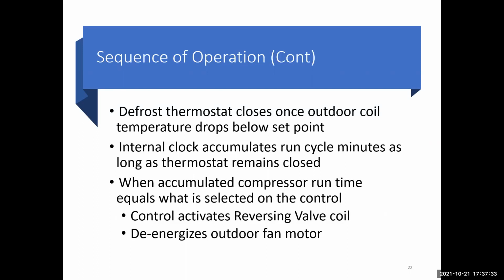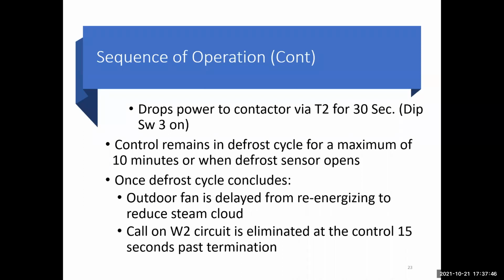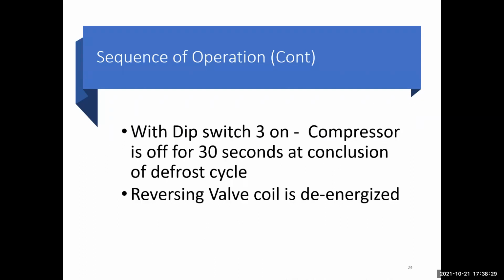When accumulated runtime equals what is selected, the control activates the reversing valve, de-energizes the outdoor fan motor, and drops power to the T2 for 30 seconds. As long as dip switch 3 is on, the control remains in defrost cycle for a maximum of 10 minutes, or when the defrost stat opens, right around 65 degrees. Once the defrost cycle concludes, the outdoor fan is delayed for re-energizing to reduce steam cloud. A call on W2 is eliminated at the control 15 seconds past termination. With the dip switch on, the compressor is turned off 30 seconds at the conclusion of the defrost.